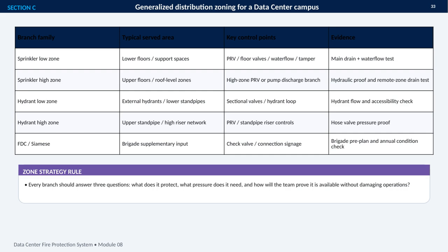The FDC, or Siamese connection, provides supplementary input for the fire brigade. Its readiness depends on the check valve, clear signage, pre-planning, and periodic condition checks. Evidence of availability comes from drain tests, flow tests, hydraulic proof, and hose valve pressure testing.